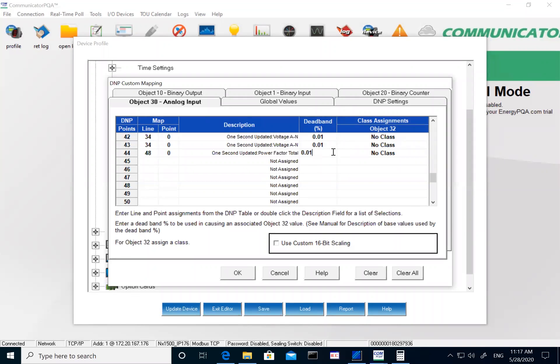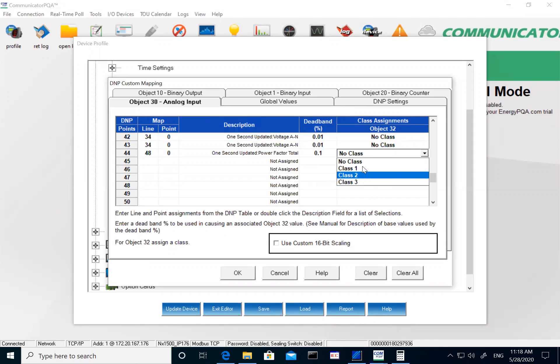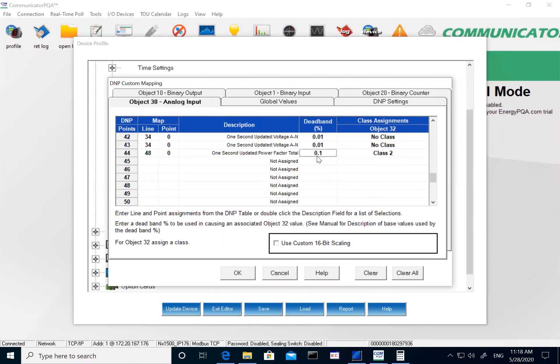Let's say I want to trigger an alarm when my power factor goes out by 0.1 percent. Anytime my power factor value goes outside this range, it triggers an alarm. I can pull it using one of the classes — say class 2. Whenever I send a signal from my RTU to read this class, the meter will respond with all the alarms triggered using the dead band.